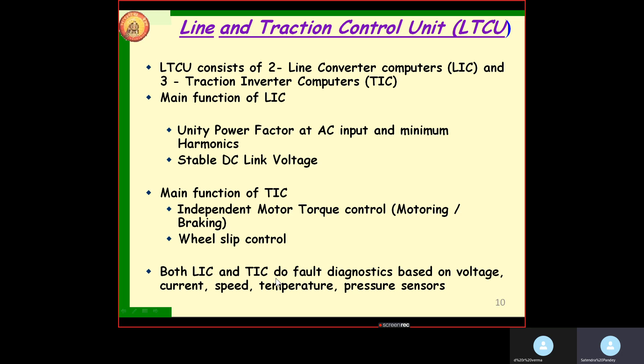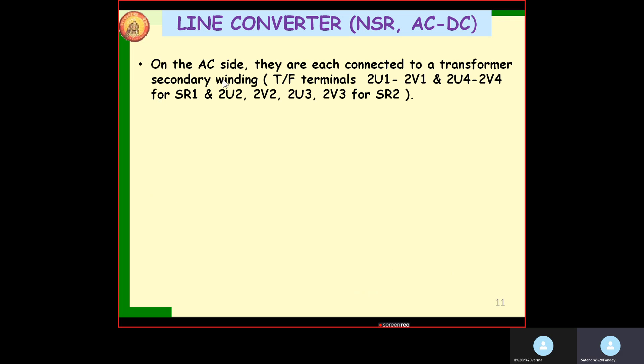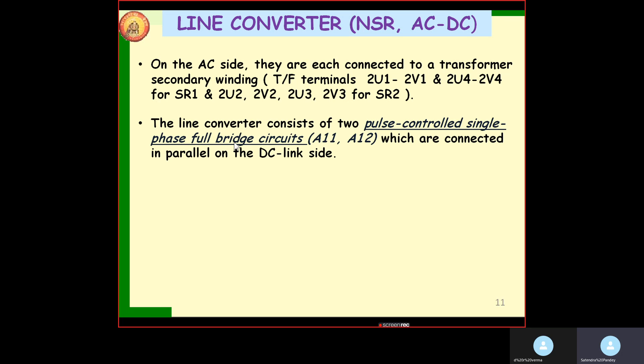Both LIC and TIC perform fault diagnostics based on voltage, current, speed, temperature, pressure, and sensor signals. On the AC side, they are each connected to a transformer secondary winding — for SR1: 2U1-2V1 and 2U4-2V4; for SR2: 2U2, 2V2, 2U3, 2V3. The line converter consists of two pulse-controlled single-phase full-bridge circuits, A11 and A12. It is self-commutating and is a four-quadrant converter.